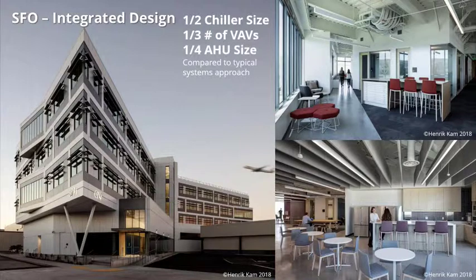The result has been we've dramatically reduced the cooling requirements of the building. The chillers are half the size that would be expected, a third the number of VAV boxes you'd expect in a building of this type, and the AHUs are a quarter the size because we're using a DOAS system - 100% fresh air - just dealing with the ventilation loads.